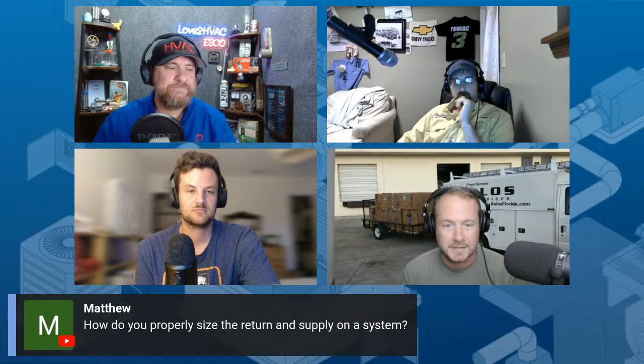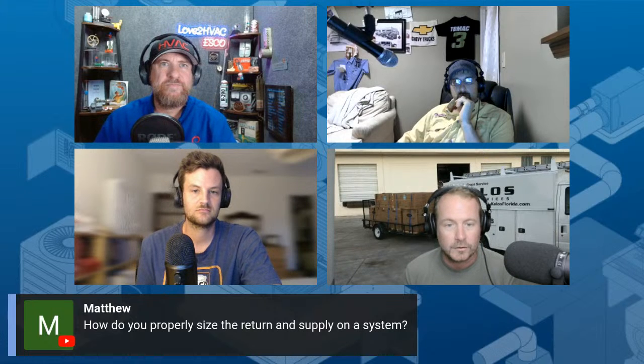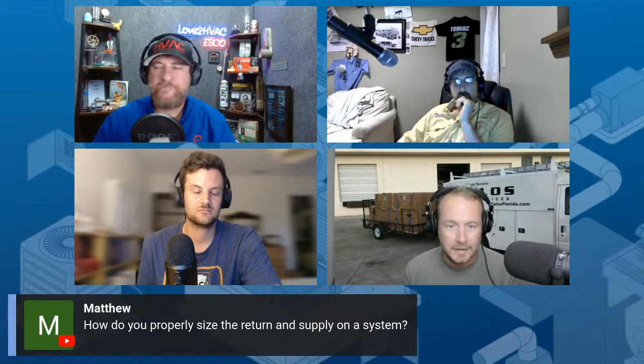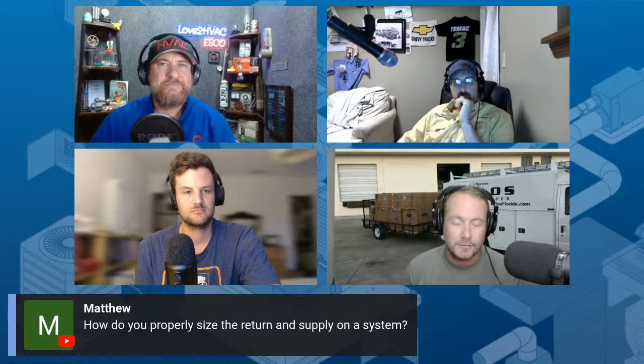A lot of that comes down to: make it as big as you can and use low friction fittings near the equipment. From there, that's where the design really starts to matter, but mostly it's dictated by size and space. If you can get bigger near the equipment, then get bigger. You can put a bigger filter cabinet in, so put a bigger filter cabinet in.